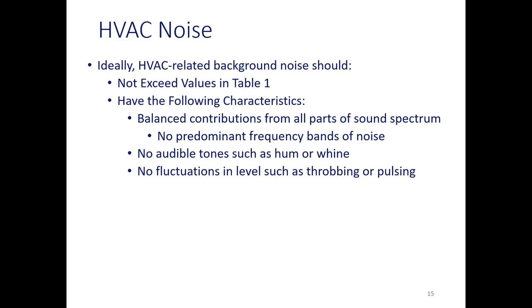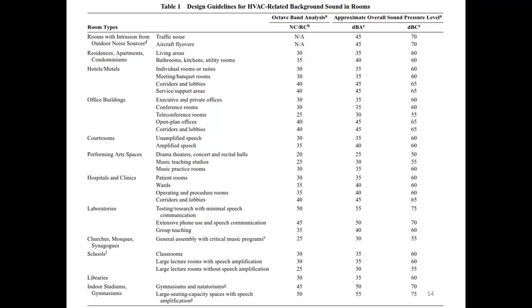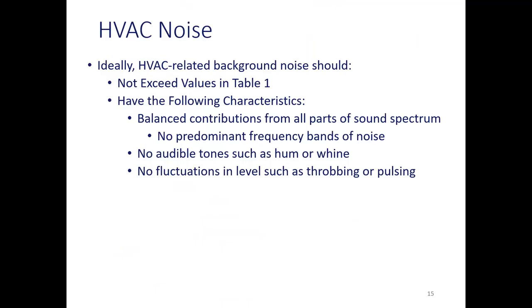So this slide here, this HVAC noise slide. We had just introduced the criteria. I'm moving backwards a slide, but this is the criteria from the ASHRAE handbook, just background noise criteria for all these different spaces. So we're saying that ideally HVAC related background noise should not exceed the values in table one. So that's the main thing, but also, and some of these will try to attempt this in a way, some better than others, it is something that a person needs to pay a little extra attention to. Like I said, with the RC stuff, the neutral spectrum is the ideal, but there might be rumbly, there might be hissy, and you need to know when that's not okay, even if the number matches what's in the table.